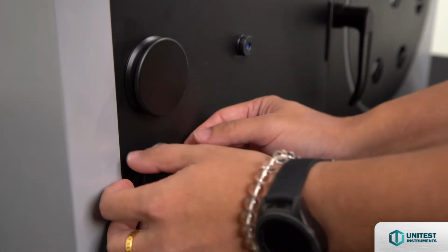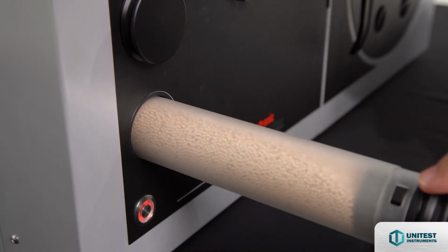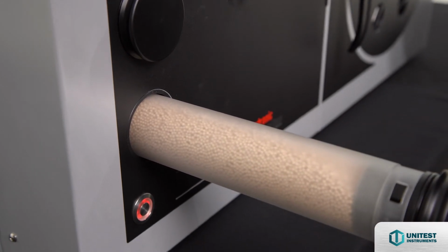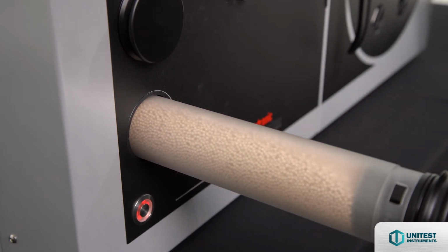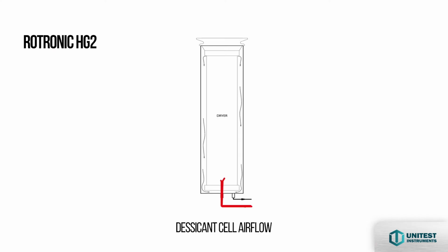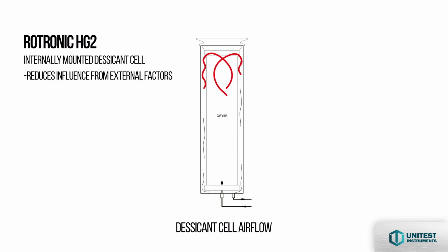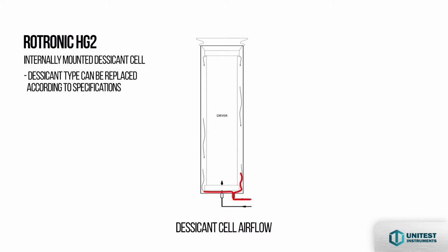A desiccant cell provides a source of low humidity, and a piezoelectric humidifier generates high humidity. The custom design of the desiccant cell in the HG2 is internally mounted, reducing influence from external factors and increasing desiccant lifespan. Users are also able to replace the type of desiccant needed according to their specifications.